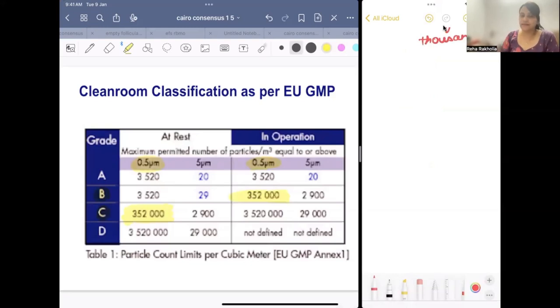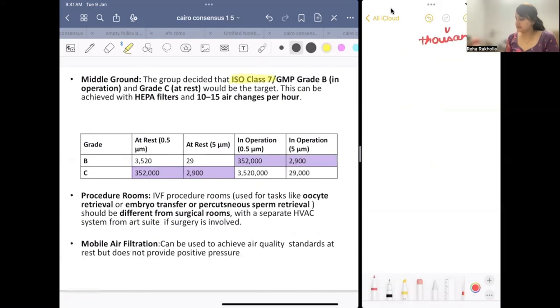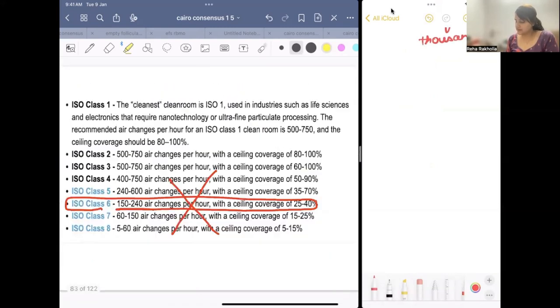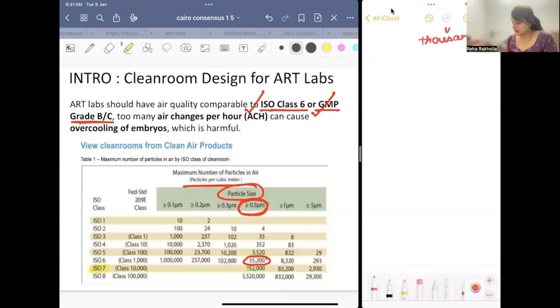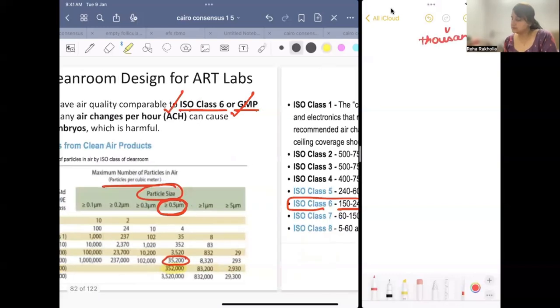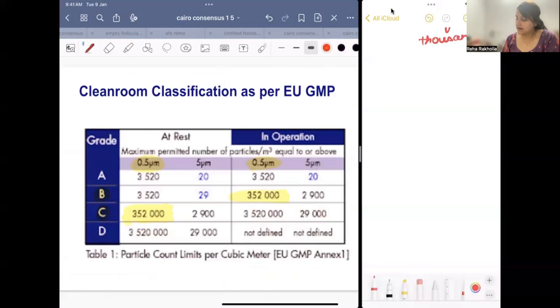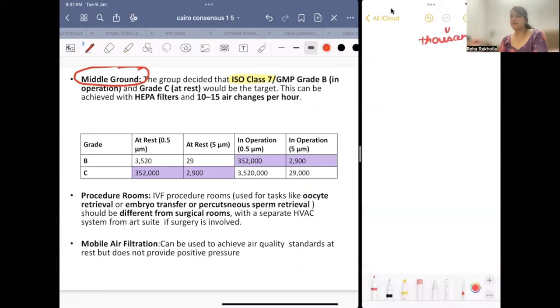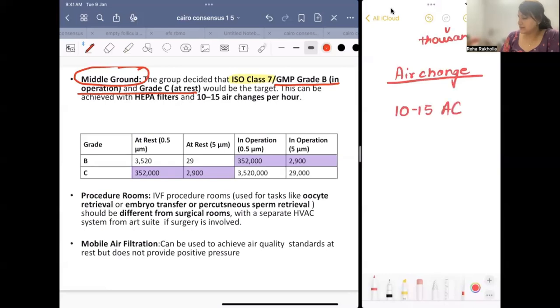Now see the middle ground, ISO 7 class. ISO 6 was very specific and difficult to maintain. So we came to a middle ground where ISO 7 is followed, with less than 3,52,000 particles of size greater than or equal to 0.5 micrometer. The same applies at rest and in operation, 3,52,000 and 3,52,000. We came to this middle ground because ISO class 6 was very difficult to maintain. This can be achieved, but we want fewer air changes, that is 10 to 15 air changes per hour.